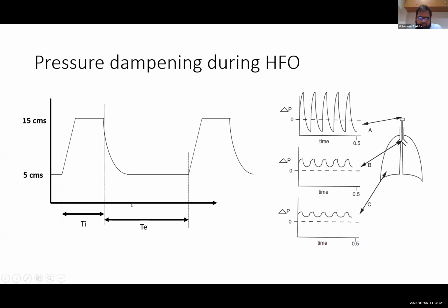So this is the I time and E time, and these are the pressures, PIP and PEEP, on the y-axis. Here the TI time we usually set around 0.35 to 0.4 seconds. If you give a very high TI time, then whatever fluctuation pressures we have given will reach the alveolar level. Whatever is generated here will reach the base of the alveoli, and this much pressure will be delivered. So a tidal volume of around 5 ml per kg will be delivered in conventional ventilation.